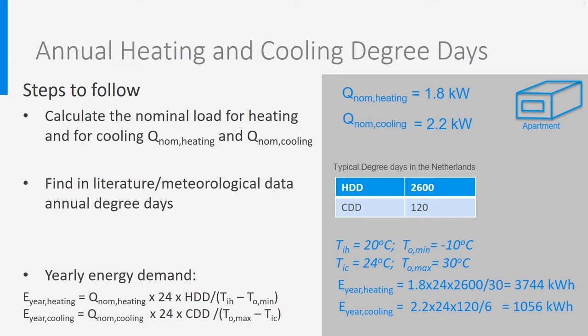T_omin is the lowest outdoor temperature used to calculate the nominal powers — in our example, minus 10 degrees. In cooling mode, T_omax is the highest outdoor temperature — we took 30 degrees. So now we can make the calculation, which leads to 3744 kilowatt-hours yearly heating demand and 1056 kilowatt-hours yearly cooling demand.